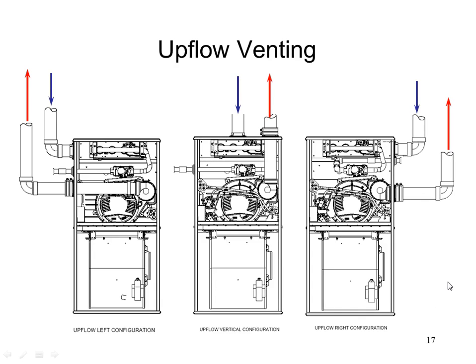From the venting scenario, this shows you the upflow configuration for these two furnaces. The middle position is how he comes shipped, so that venting elbow is pointing upward. So the exhaust would be going up and out. The intake is coming in on the top, although he could come on the left or the right side for the intake as well. Once the intake comes to the cabinet, he terminates there, and then he brings air into this whole cabinet and pressurizes it.